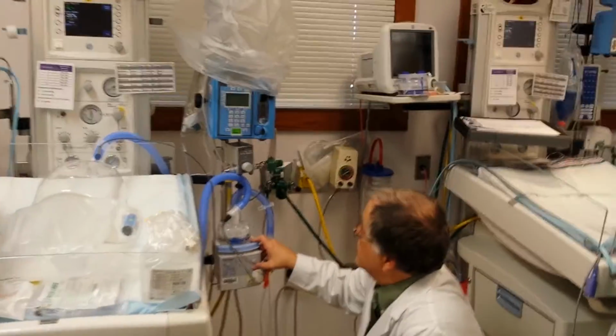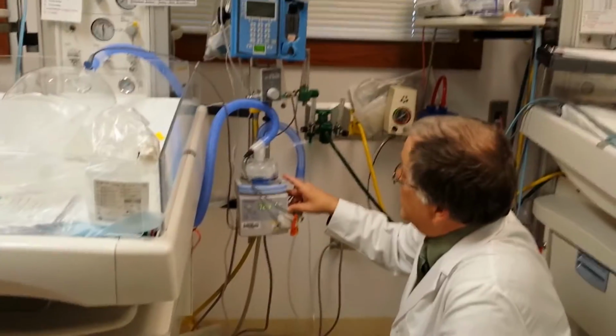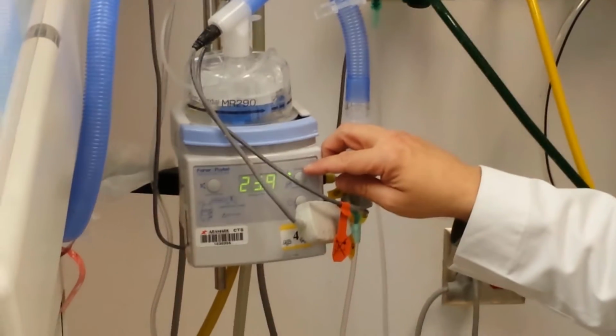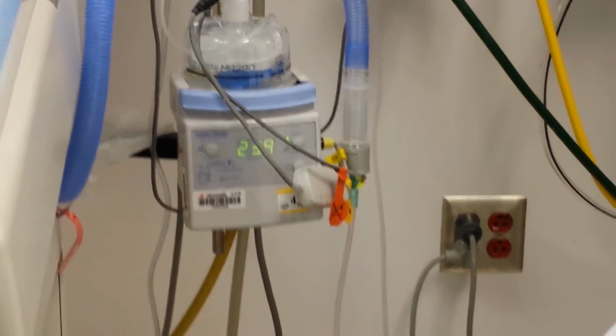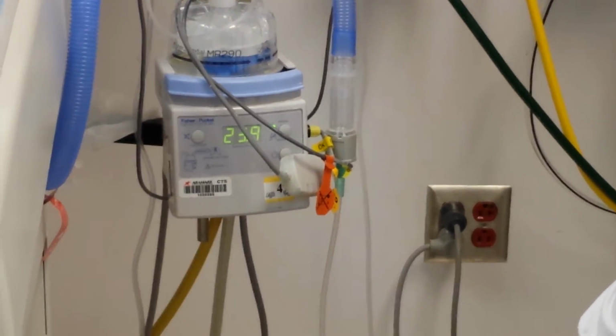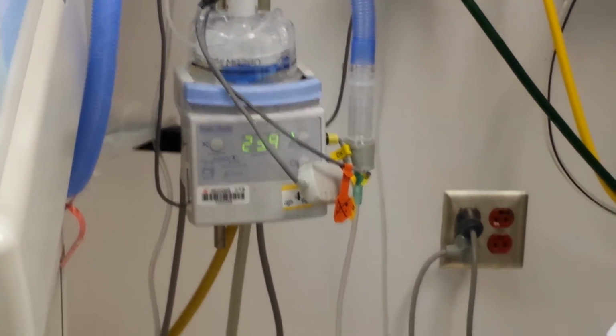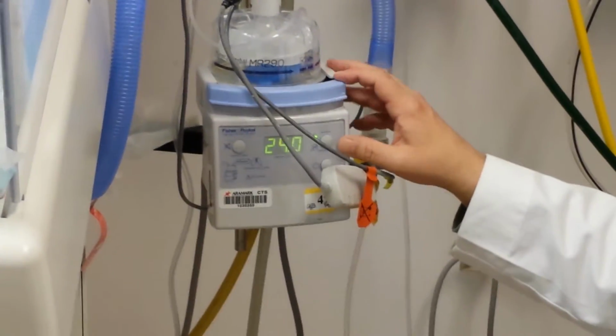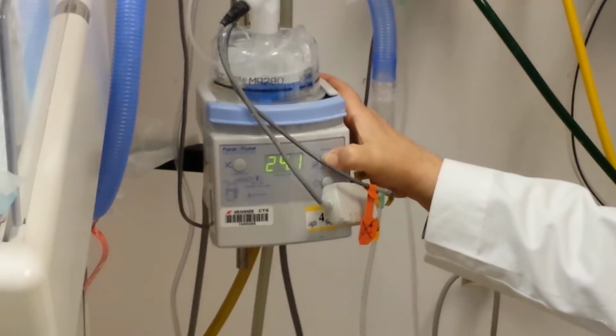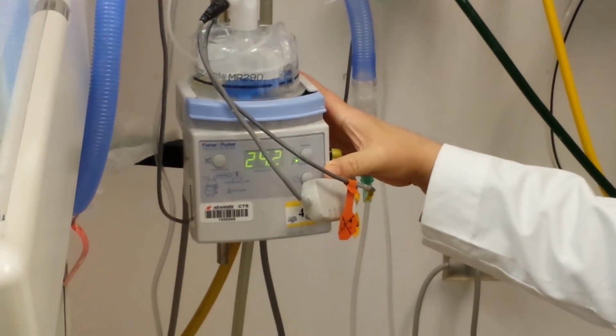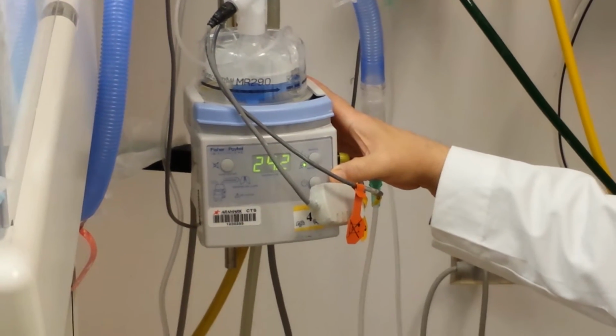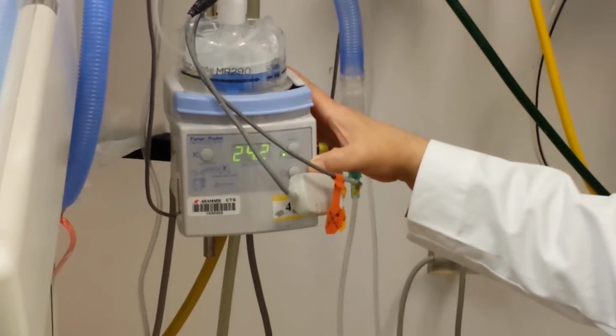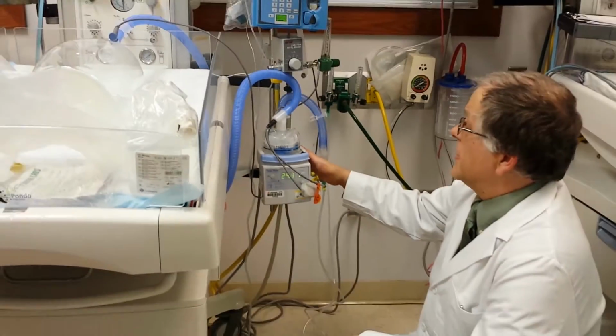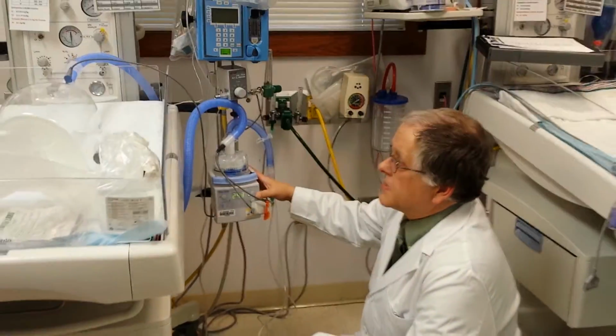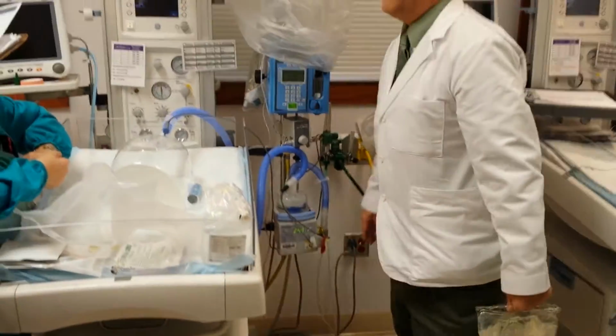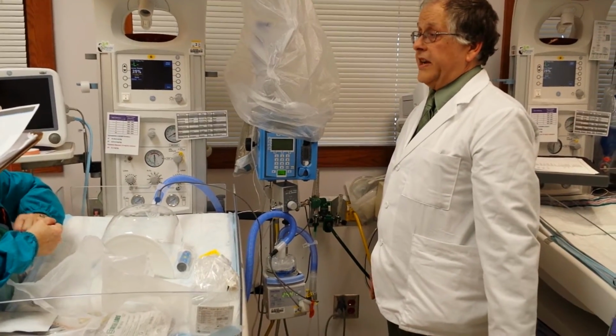You turn the power on here, and it goes automatically default to the higher temperature setting, which is the invasive mode. If that's too warm or it gets foggy and it's safe to turn the temperature down, you hold this button for about 3 seconds, and it goes to the non-invasive mode, which is about 7 degrees cooler. Okay, invasive is 37. I think the non-invasive is about 30. So, just depends on your baby, but if they're premature, they probably need a higher temperature than you get.